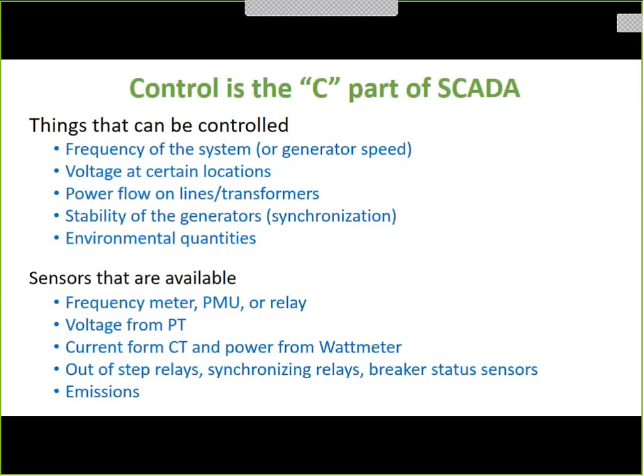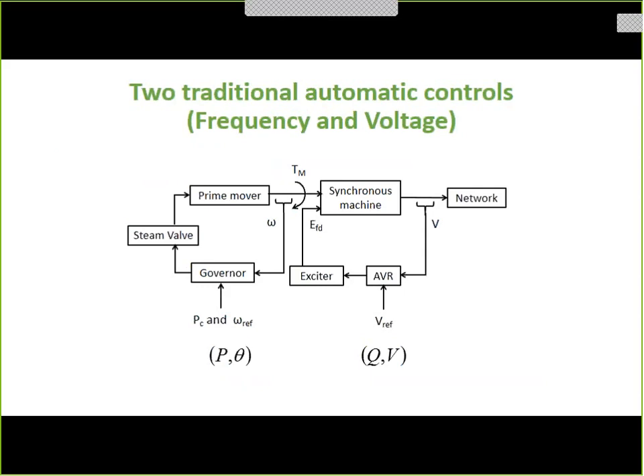We used to call it NOx and SOx. And this was really popular in the 70s when there was acid rain. And there are a lot of laws about pollution now that have to be a constraint here. The sensors that we have, frequency meters, PMUs, relays, PTs and CTs, out-of-step relays will sense that you have lost synchronism. Florida lost synchronism with the eastern grid. That used to happen all the time. Literally, Florida separated away from the eastern interconnect because it couldn't remain stable. Whenever we try to connect the east and the west together synchronously, it never works. We have to open it up. Okay, emissions is another one.